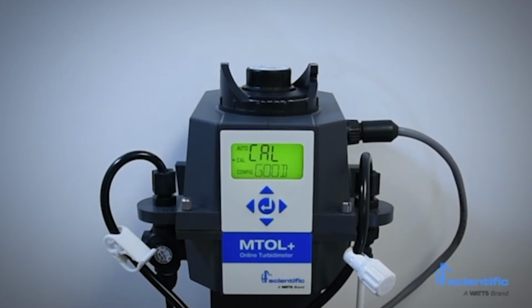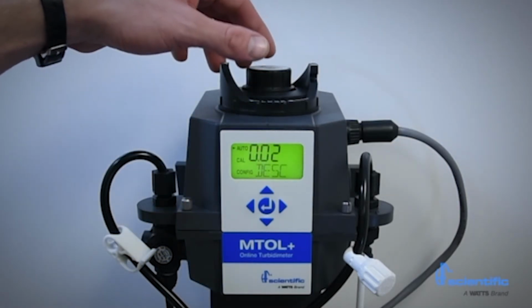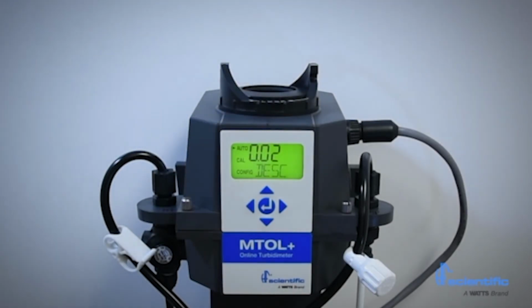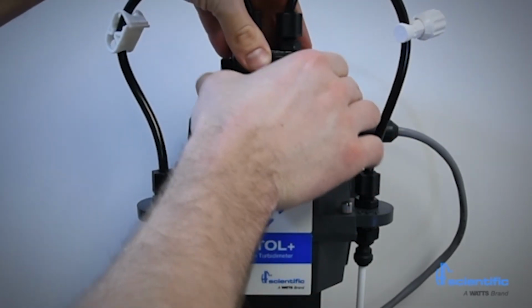The calibration process is now complete. The MTOL+ will automatically enter the auto mode for routine turbidity measurement. The MTOL+ only stores successful calibrations. If a calibration fails, the instrument will use the last valid calibration.